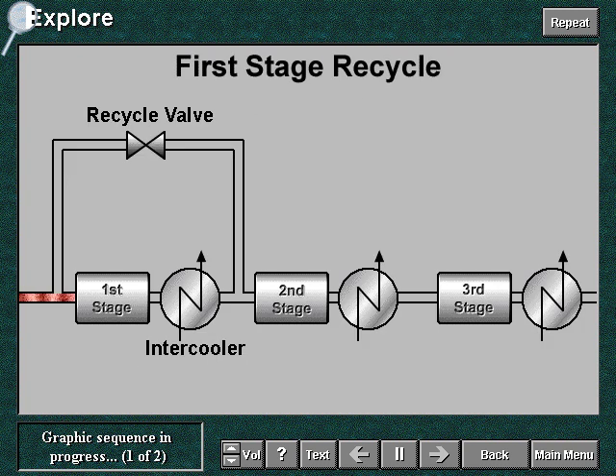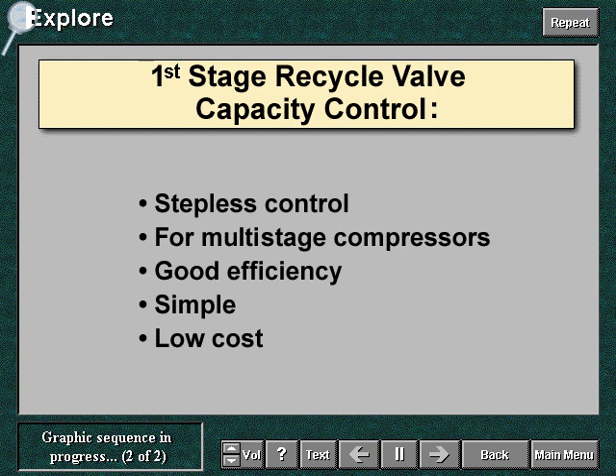Recycle controls capacity by recirculating a portion of the gas from the first stage delivery back to its suction. This system is suitable for multi-stage compressors and works by reducing with the recycle the quantity of gas that is sent to the second stage and beyond. The gas amount recycled around the first stage can be varied continuously. The system therefore is a continuous type control. The first stage handles 100% of the gas under capacity control, but the following stages handle only the reduced flow rate. Therefore, the efficiency of the system is good and increases with the number of stages. First stage recycle is simple and of low cost.